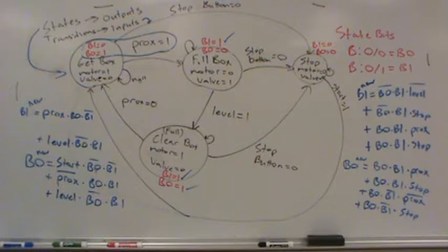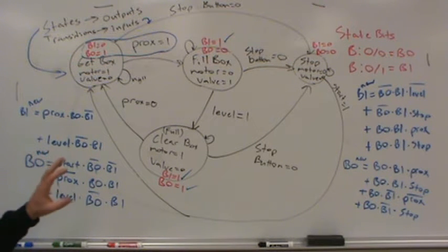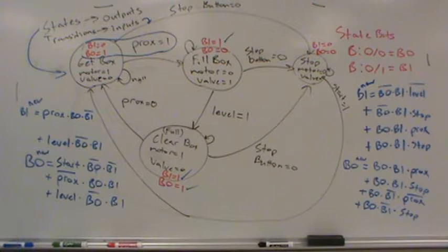So, it's a little bit of a long process, but do you see how developing the algorithm is more about deciding what states the machine should be in and when it should transition between the states? Which is a really nice way to develop an algorithm, because it's basically the same algorithm every time. Just leave the machine in a particular state, let it keep doing something until that task is done, like filling the box, and then move on to the next step. Okay? Which is really nice.